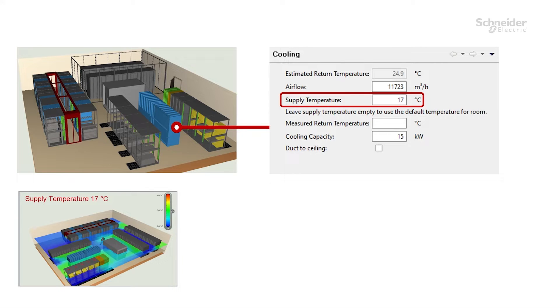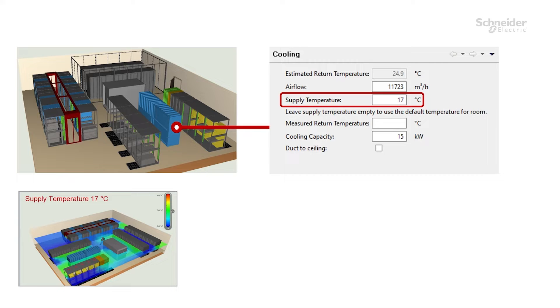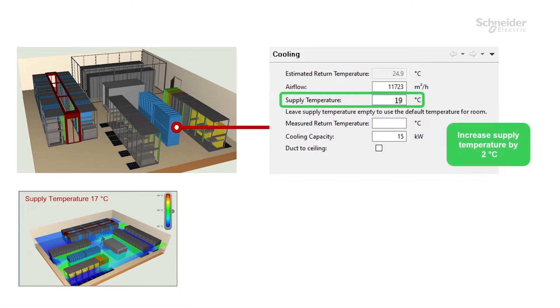Now we could possibly simulate and change the supply temperature inside IT Advisor to investigate if the situation is going to change once supply temperature is increased, for example with 2 degrees Celsius, reaching 19 degrees Celsius.